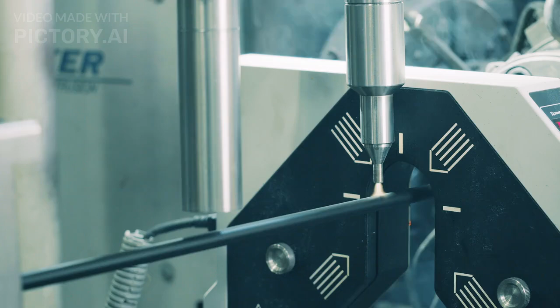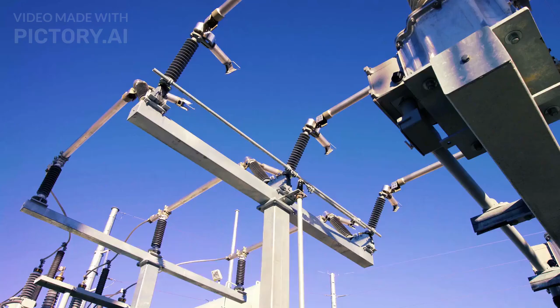6. Calculate voltage drop. Use the formula V_drop = (2 × L × I × R) / 1000, where L is the cable length in meters, I is the current, and R is the resistivity of the conductor material.